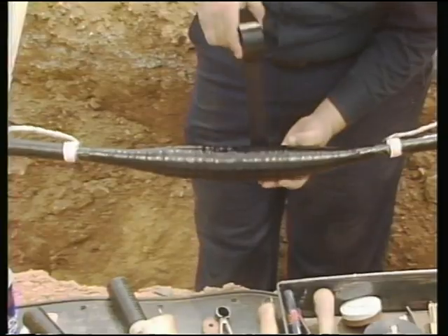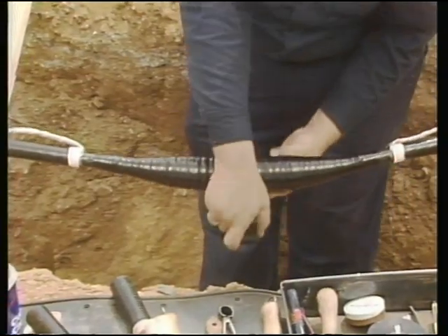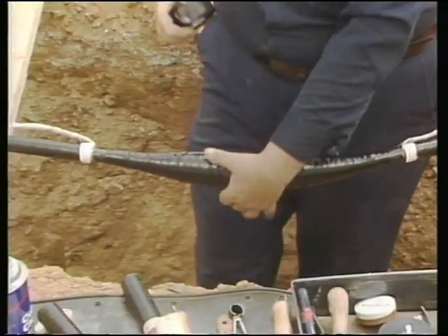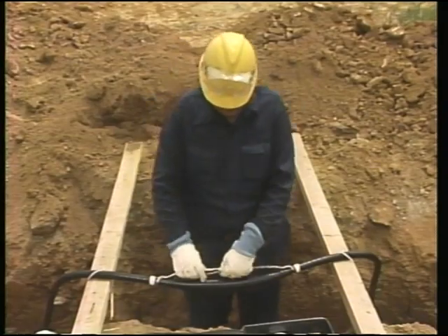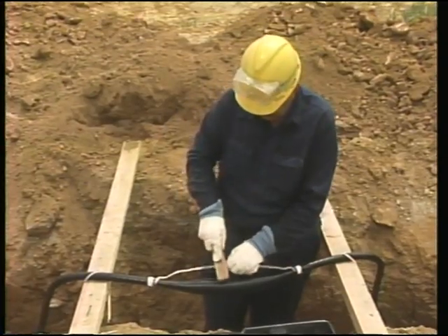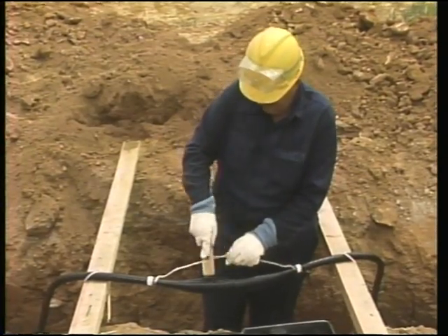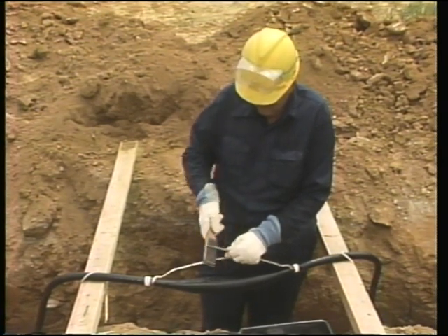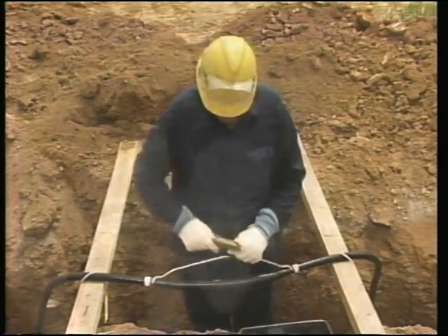Next, a layer of rubber tape is applied over the copper shielding. Its purpose is to protect the copper shielding and prevent it from damage. Now, the last step before replacing the cable jacket layer is splicing the concentric wires together. The ends are brought together and then brushed clean to ensure good electrical contact.